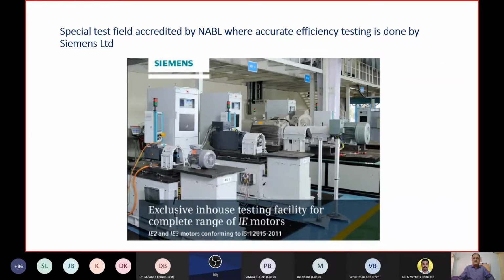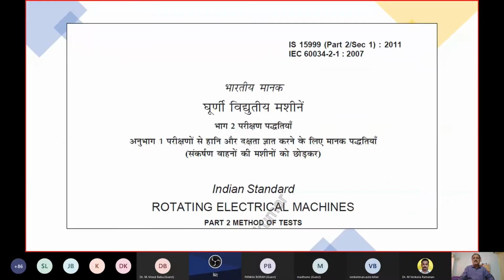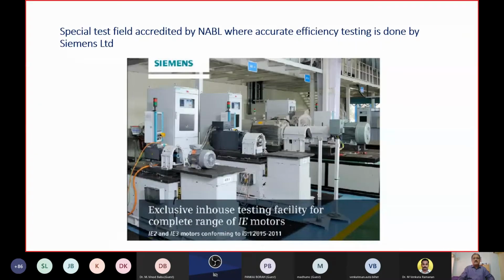This standard, I have used a slide from Siemens Limited, who have put up, to now, in my opinion, the only lab where they can test these motors with the residual loss method, which is the only method recognized by IEC 60034-2-1 in 2014. So this lab can test motors up to 3 megawatt. Only lab in India which is accredited by NABL, and the testing is done. And this lab cost Siemens approximately 70 crore investment, just for information on the side.